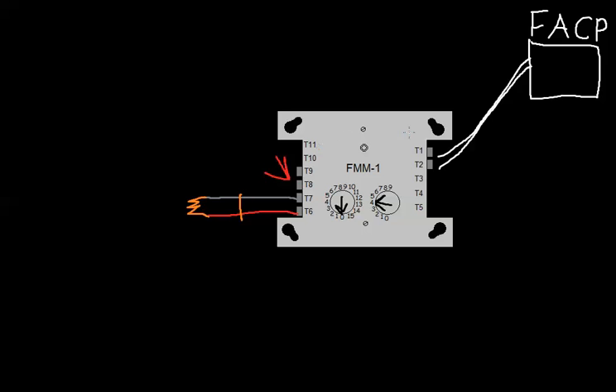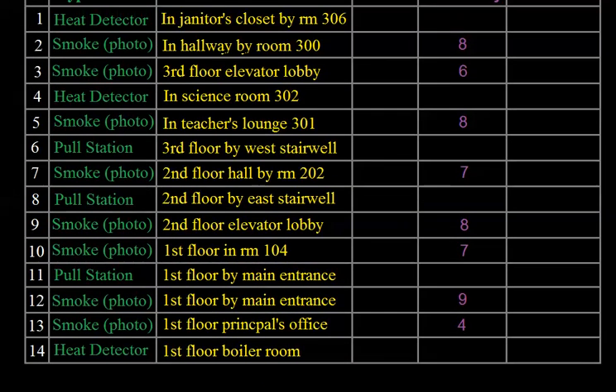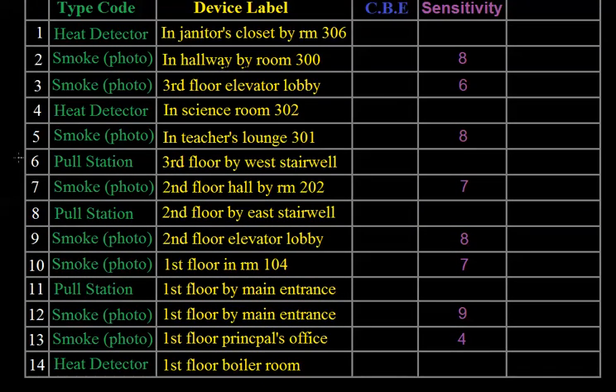This module then tells the panel, 'Device four is activated.' Whatever it was programmed as — say a water flow — the panel would use that information. Imagine device four on the spreadsheet was programmed as a water flow for room 302. The panel is going to say: alarm, water flow, room 302, et cetera.